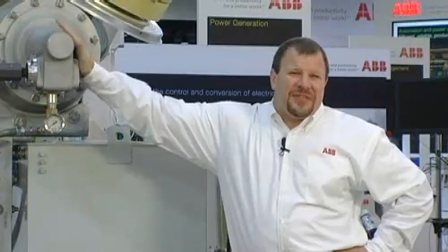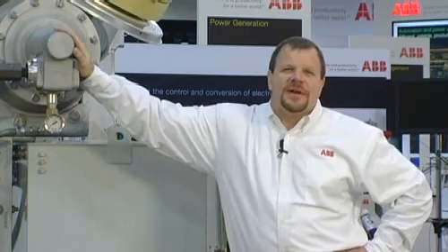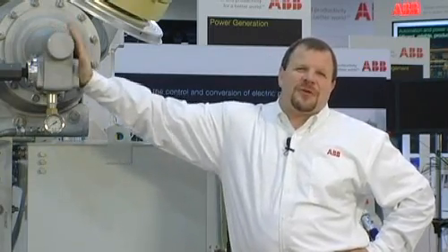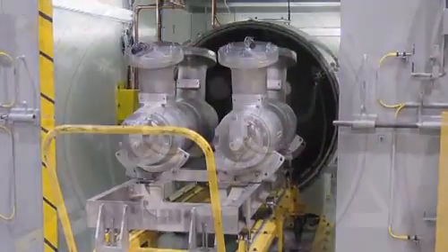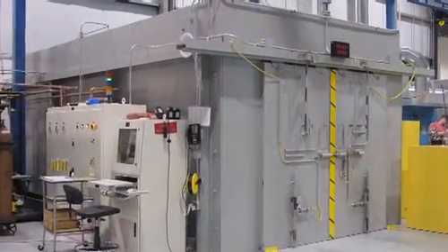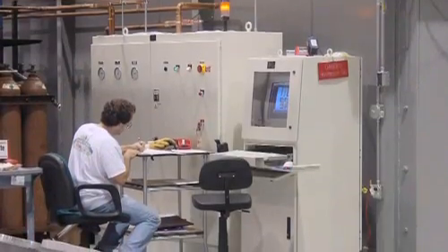breaker. The second thing utilities can do to help reduce the SF6 gas losses in their breaker systems is to make sure as the breakers are going through a manufacturing process, they're being tested to the most stringent standards they can have done. For example, one of the things that can be done is they can go through a helium mass spectrometry leak test that not only will test the sealing systems within this phase, but also it tests the porosity levels that go on with inside the tank.